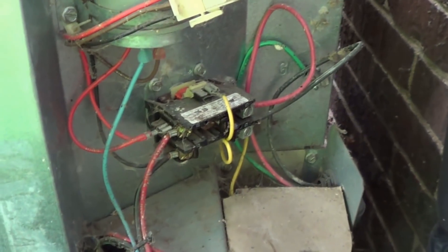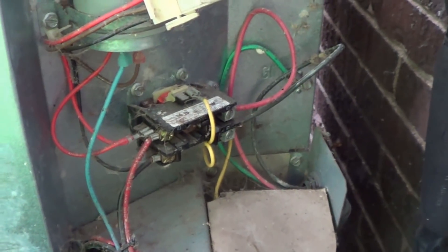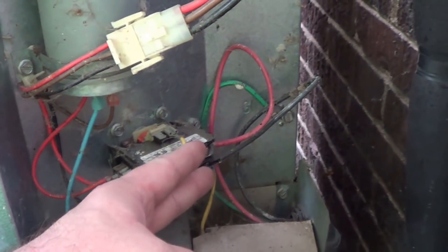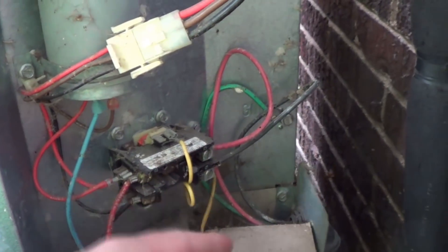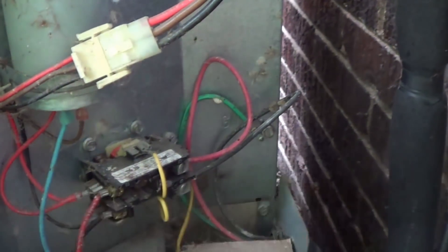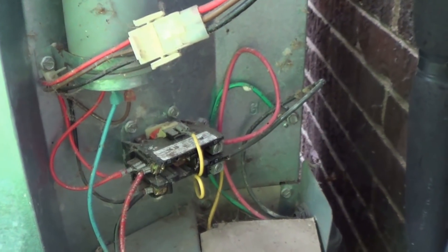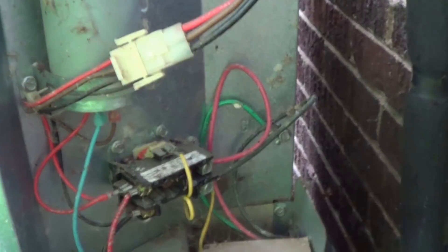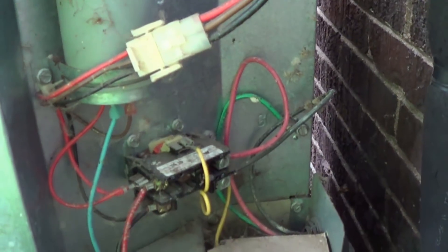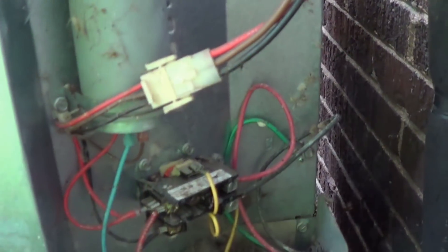I'm sure some clever clogs in the viewing audience is going to call me on this: to make a complete voltage check at the outdoor unit to make sure that everything is dead, especially if one of the two fuses protecting it has blown, you need to go not only between the two legs of power, you also need to go between each leg of power and ground. And if you're not sure you can trust the ground in the unit, drive a metal rod or a piece of copper pipe into the ground about a foot or two in most places with average soil types, run a wire to that, and you can use that as your ground reference while you check for power on either side. So don't just check across these two contacts — check across them by themselves between each one and ground.